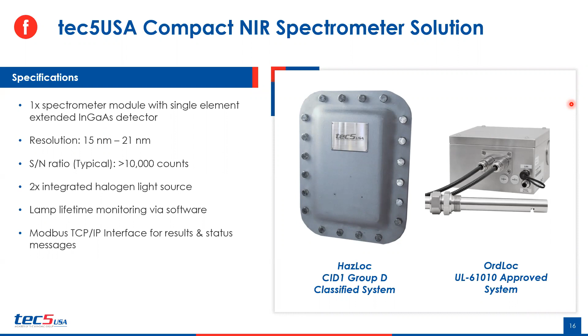I mentioned previously the miniature halogen lamp. This has a very compact design, as all the other portions of the device do. And it's also built, as you can see, with these two dual halogen light sources here. So the functionality of these dual light sources is to automatically switch from one light source to the next if there's any kind of intensity drop. So this intensity drop could be due to just the lifetime of the lamp degrading over time, or an intensity drop due to lamp failure or any other kind of failure. And automatically the secondary device or the backup device would initiate, and you would not have a loss in measurement.